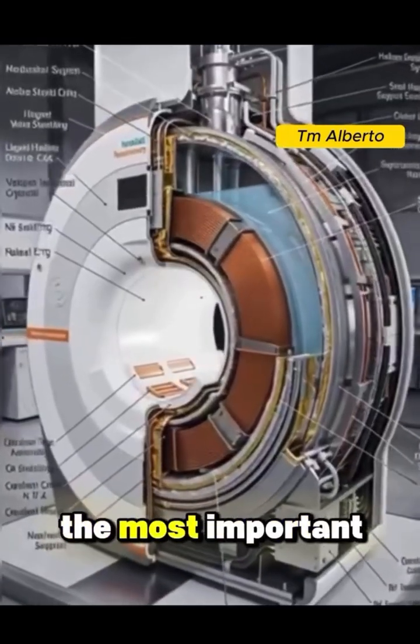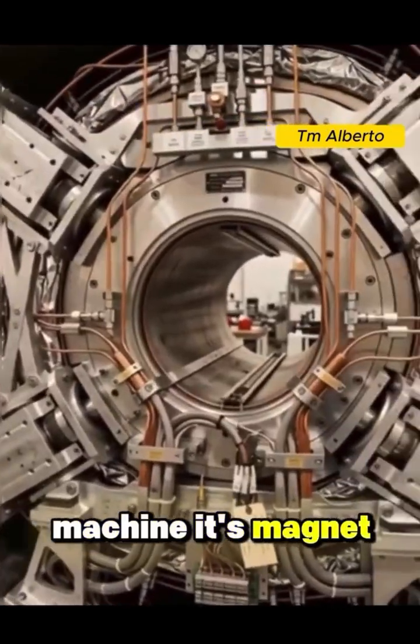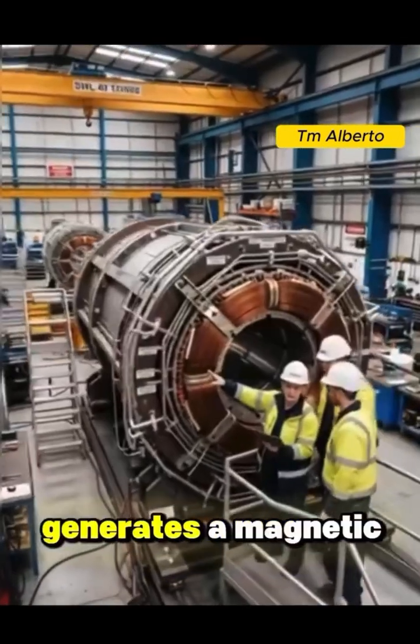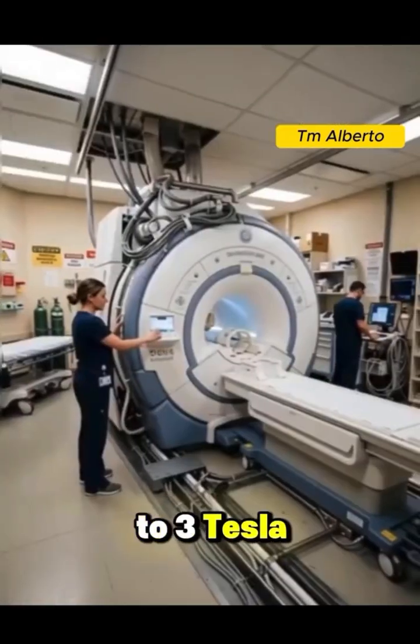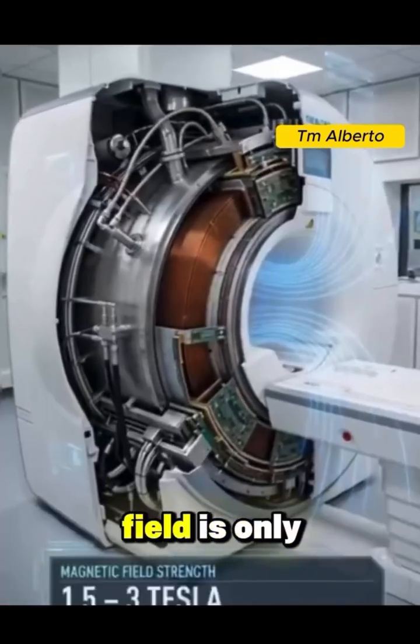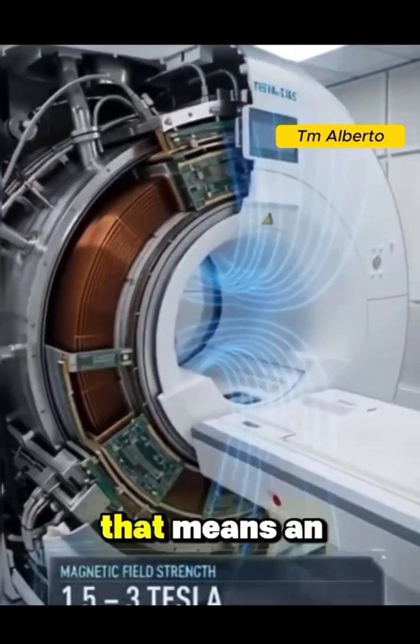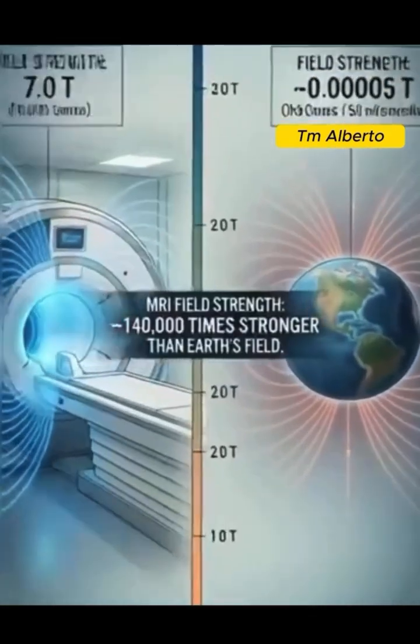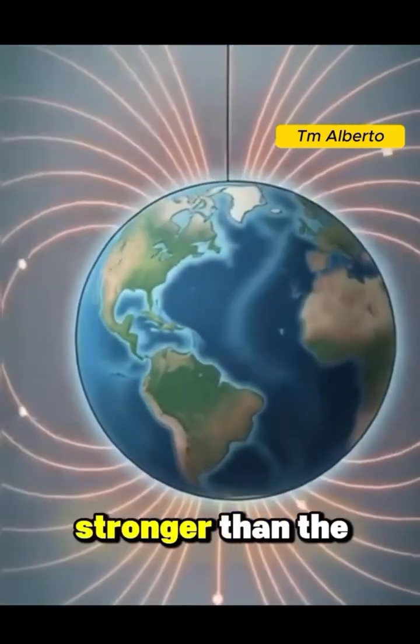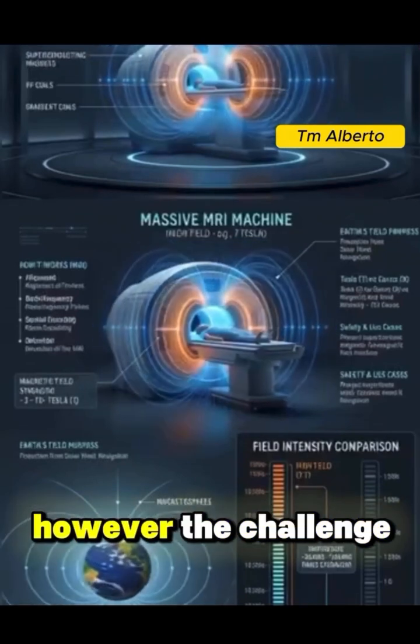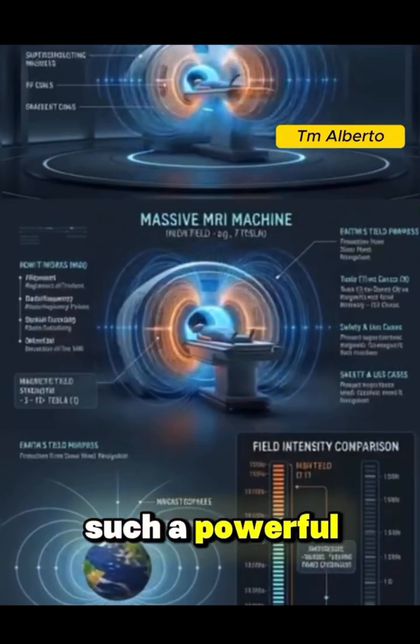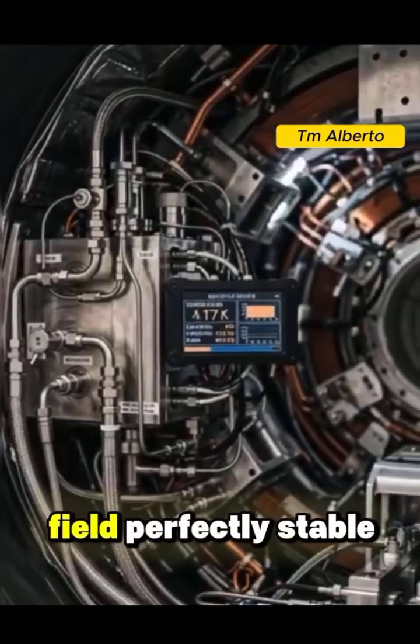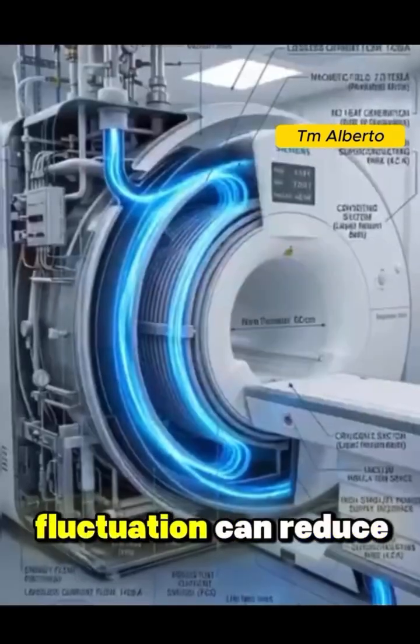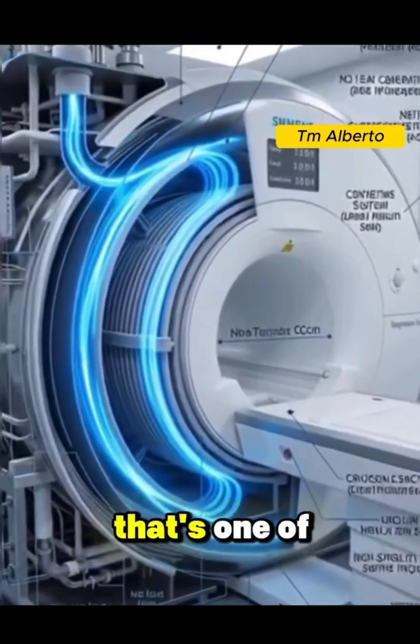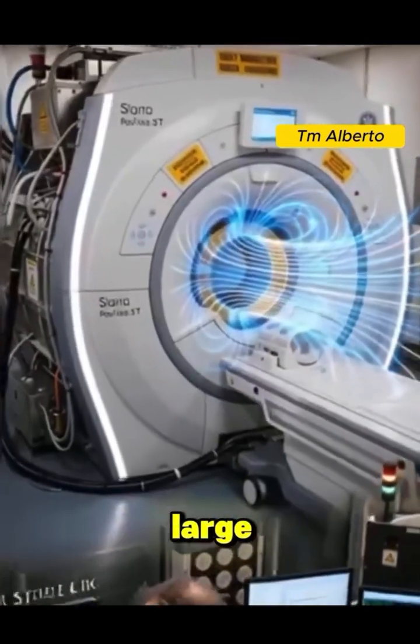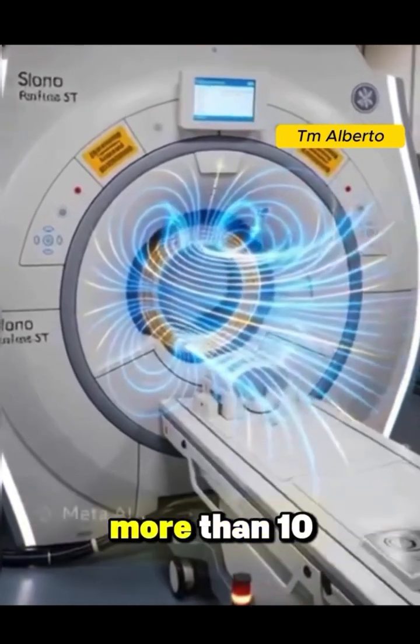Let's start with the most important component of an MRI machine, its magnet. A standard MRI scanner generates a magnetic field of 1.5 to 3 Tesla. For comparison, the Earth's magnetic field is only about 50 microteslas. That means an MRI magnet can be 30,000 to 60,000 times stronger than the Earth's magnetic field. However, the challenge isn't simply producing such a powerful magnetic field. It's keeping that field perfectly stable. Even the slightest fluctuation can reduce image quality. That's one of the reasons MRI machines are so large and heavy. Some MRI scanners weigh more than 10 tons.